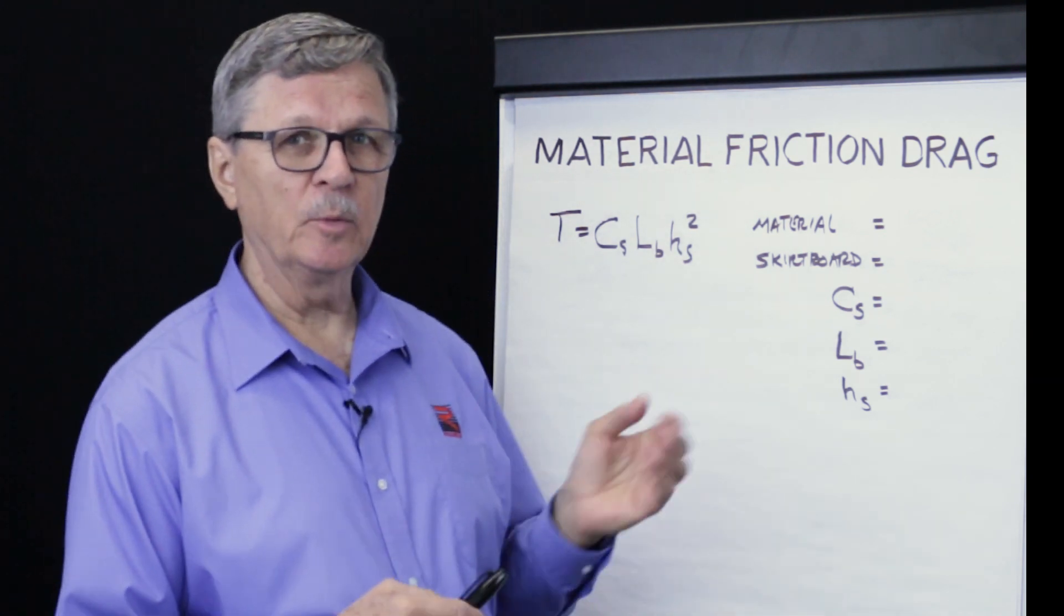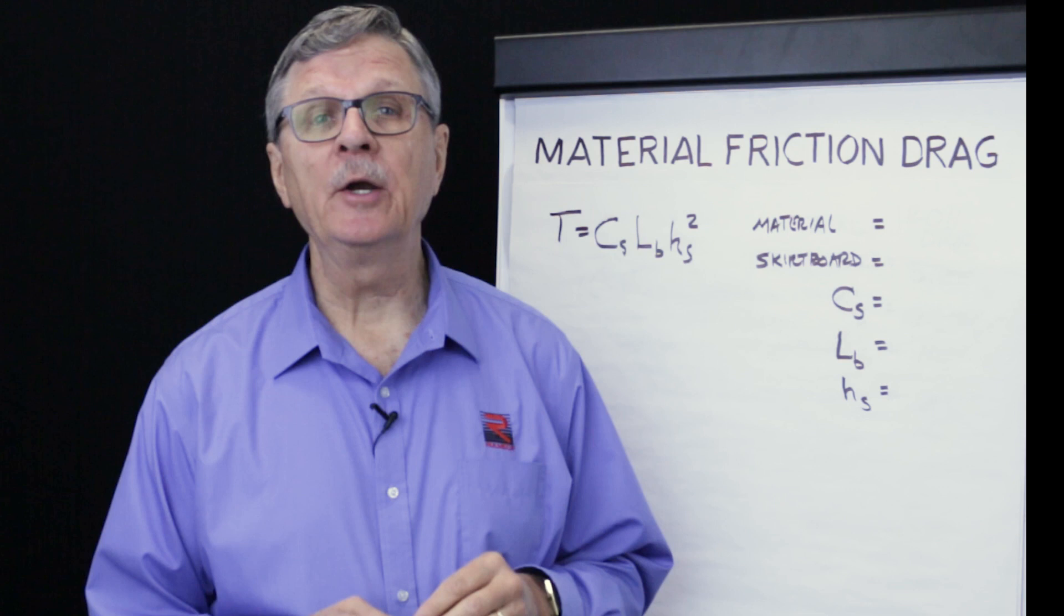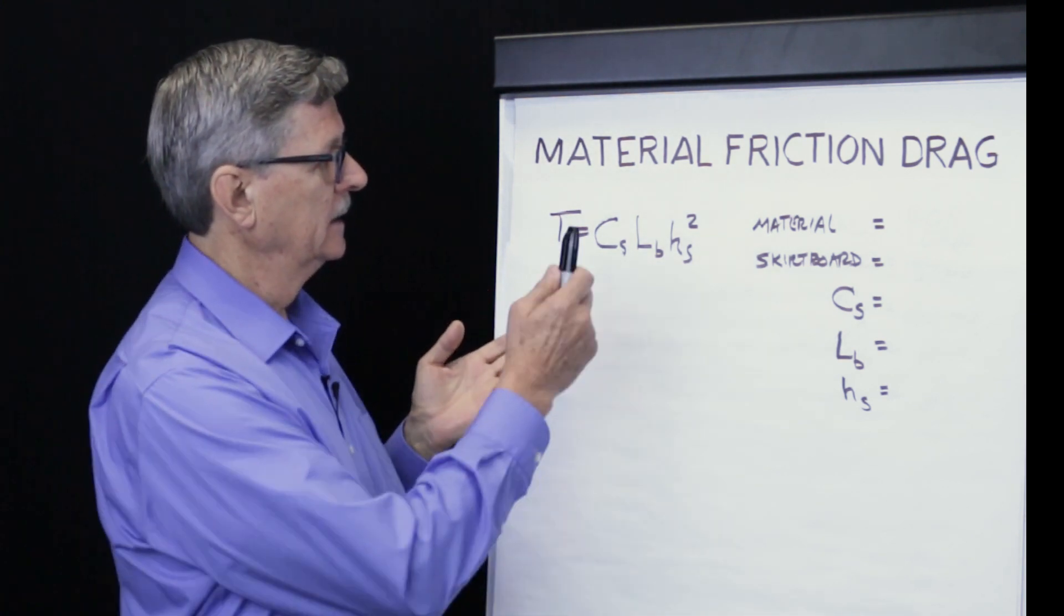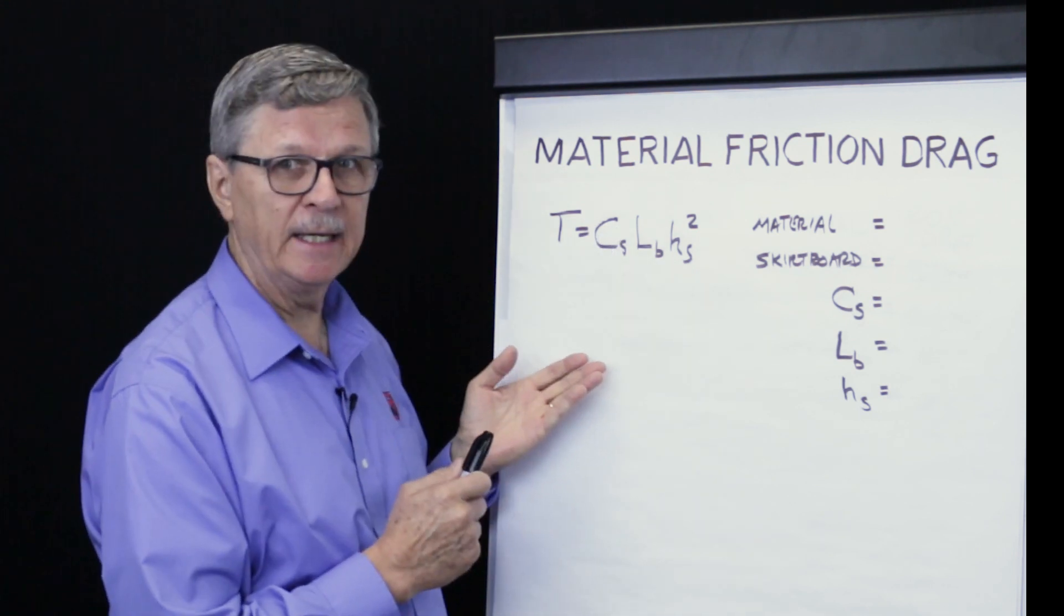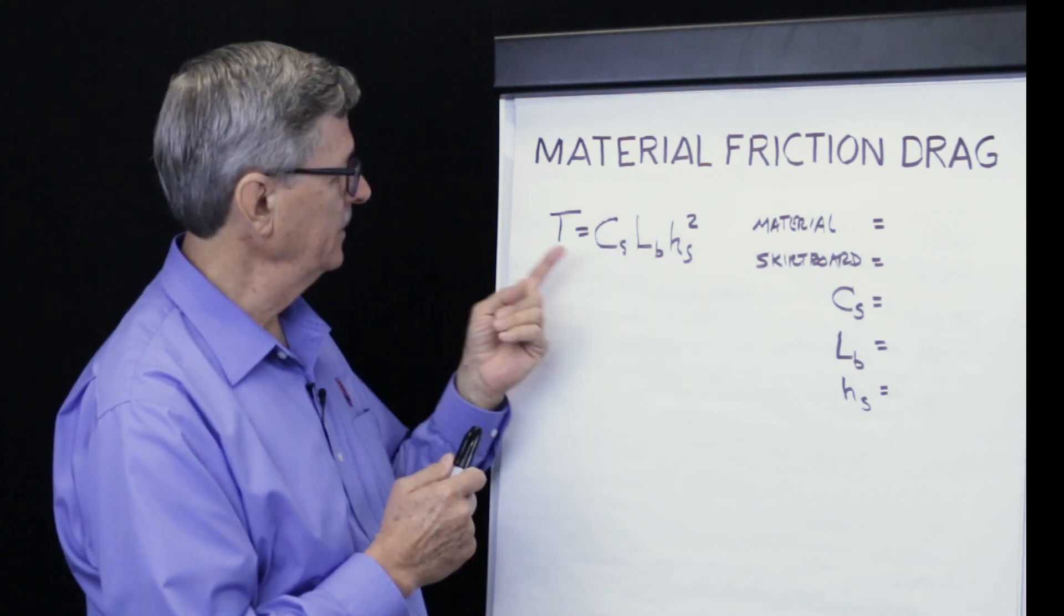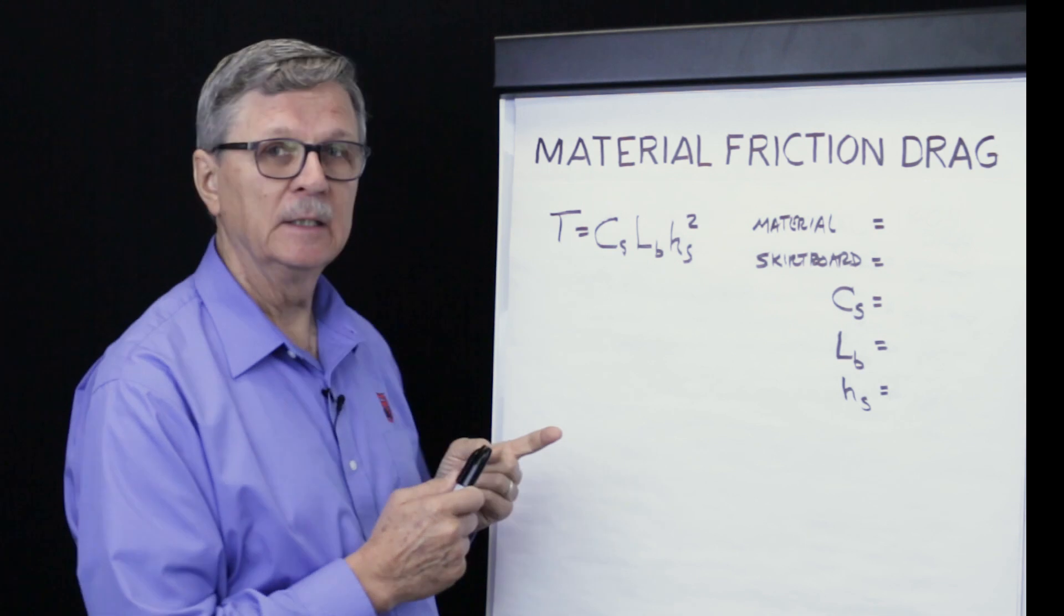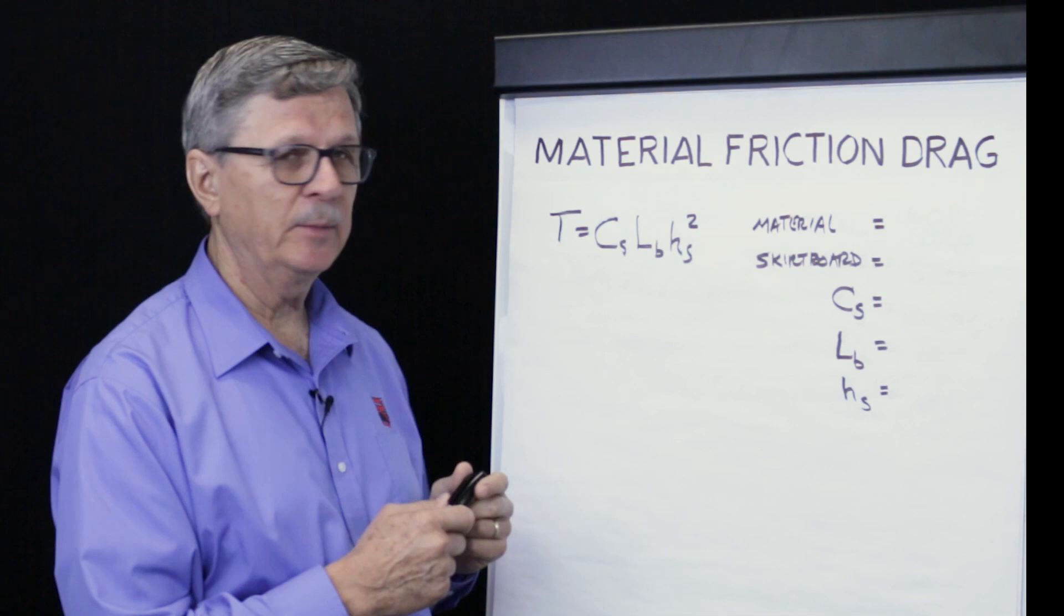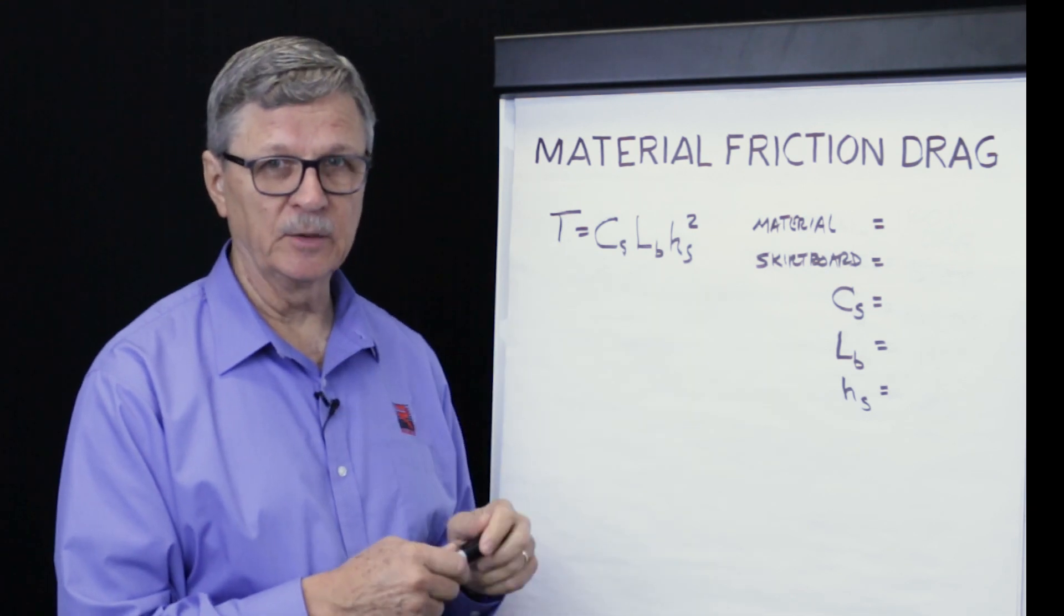In this example, we're going to move iron ore. So to calculate frictional drag from the material rubbing against the skirt board, we simply multiply the frictional coefficient times the length of the skirt board times the square of the material depth within the skirt zone.